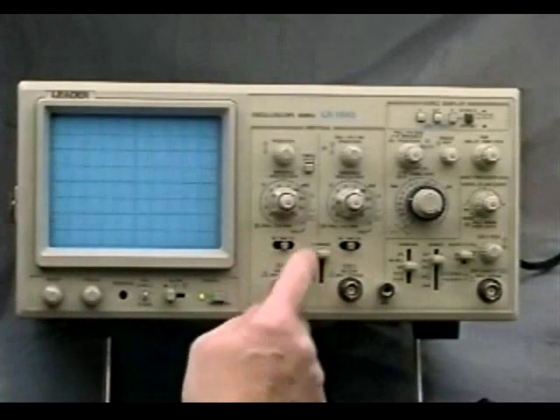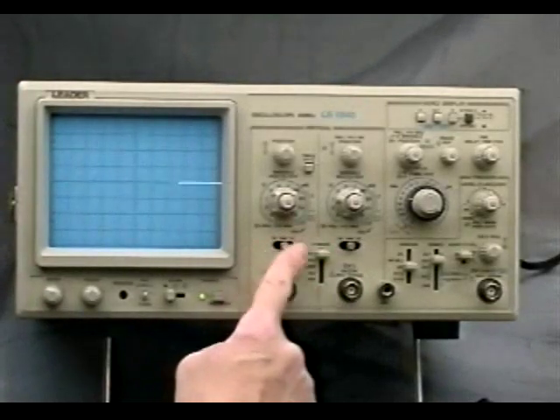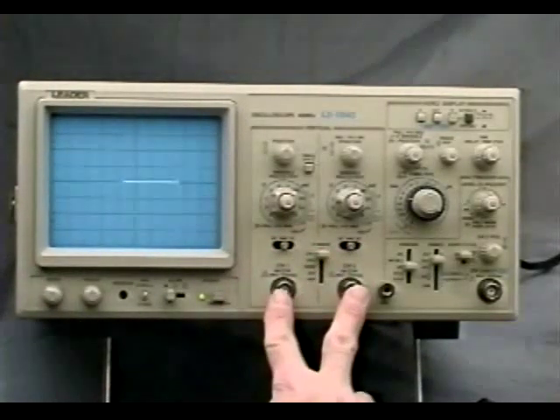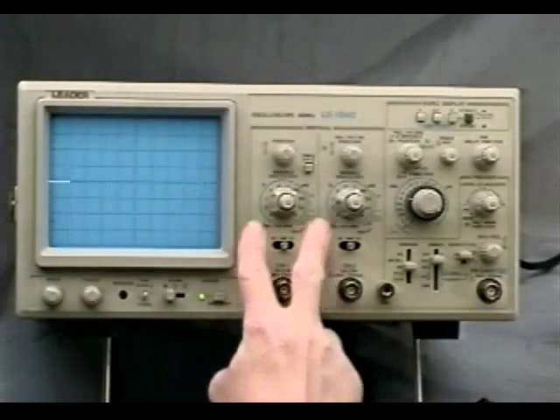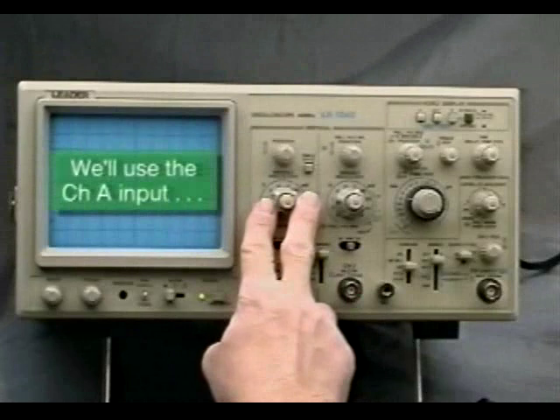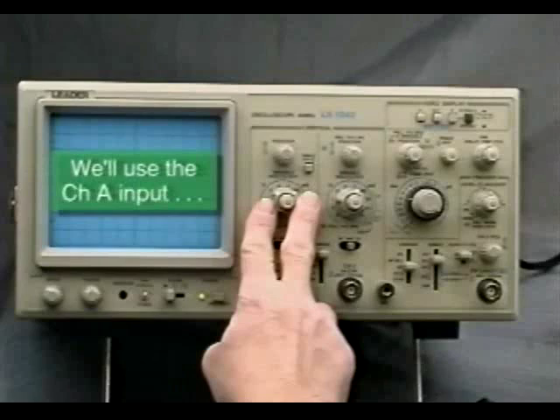Since this is a dual-channel oscilloscope, we have two identical input coupling switches and two identical input VNC connectors. We're going to use the channel A input, and with it, channel A's vertical attenuator and vertical position controls.